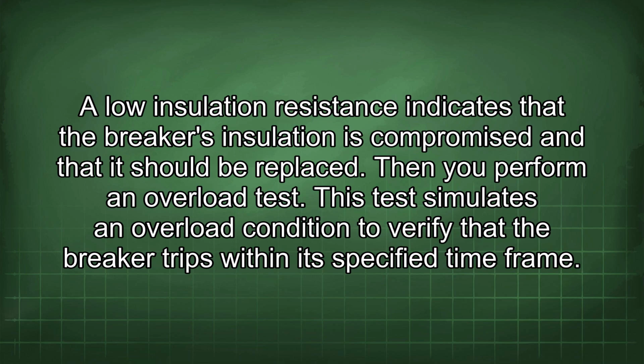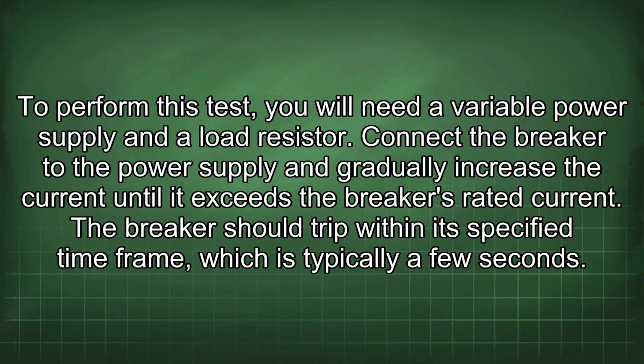Then you perform an overload test. This test simulates an overload condition to verify that the breaker trips within its specified time frame. To perform this test, you will need a variable power supply and a load resistor. Connect the breaker to the power supply and gradually increase the current until it exceeds the breaker's rated current. The breaker should trip within its specified time frame, which is typically a few seconds.